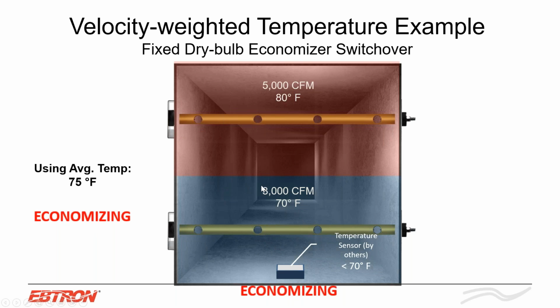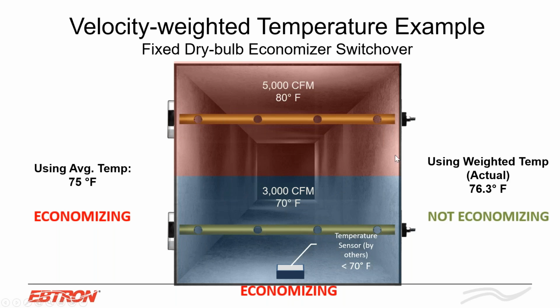But if you use our velocity weighted calculation, which is inherent for all of our devices, we're saying there's almost twice as much airflow at the top of the duct based on the bottom of the duct. So we're weighting more value to the top of the duct, right? So using the velocity weighted calculation, you would actually be at 76.3, and you should not be economizing. So when you were economizing, you were actually rejecting air that cost less to condition, right?